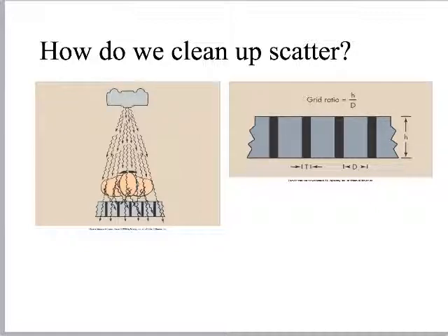That will get you pretty close to where you need to be. So if we're changing from having a grid to not using a grid or whatever, we have to divide out some stuff. And we can drill down more into that in Symposium on Friday. But just know that we do have to increase, just to go from no grid to having a 5 by 1 grid, we've just doubled the patient's dose. We've had to increase mAs enough to double the patient's dose.